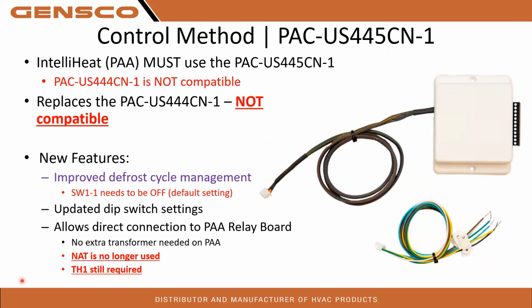This is the PAC 445. Again, the 444 is not compatible. So if you've got any of those lying around, they're not going to work for this. With the 445, they did make some improvements to the defrost cycles. In order for those changes to take effect, SW1 number 1 needs to be turned off on the dip switches inside this thing. If you turn that back on, you're going to change the defrost cycles back to what we were having on the 444s, and you could potentially have some issues with defrost on these things.